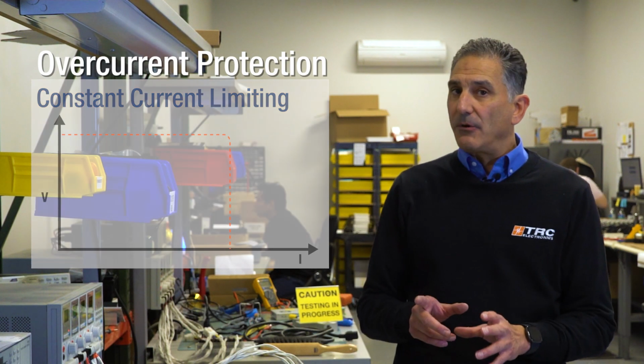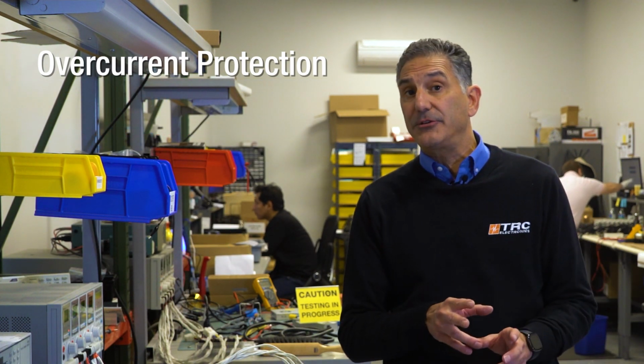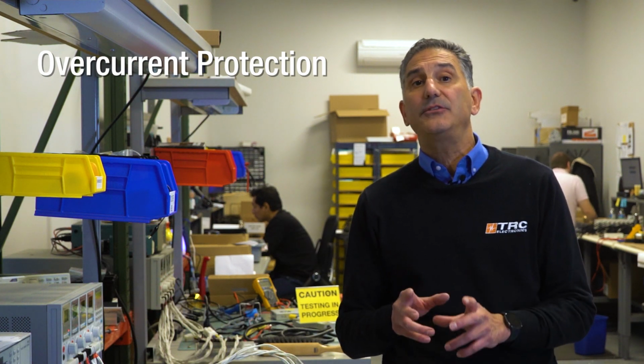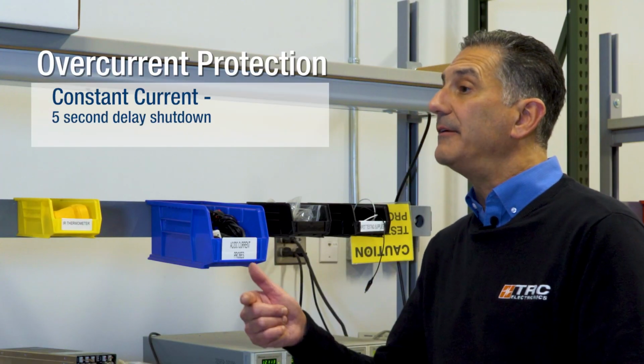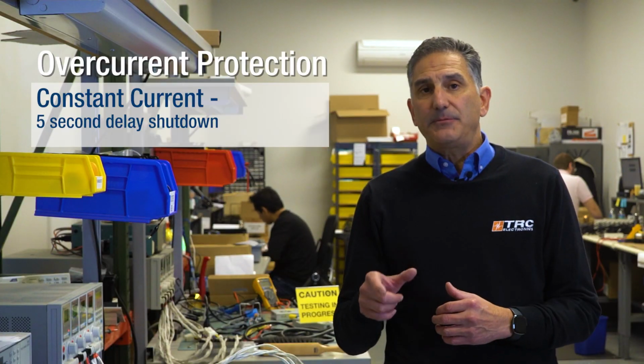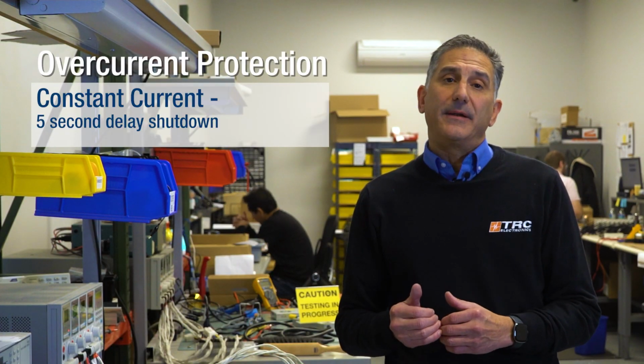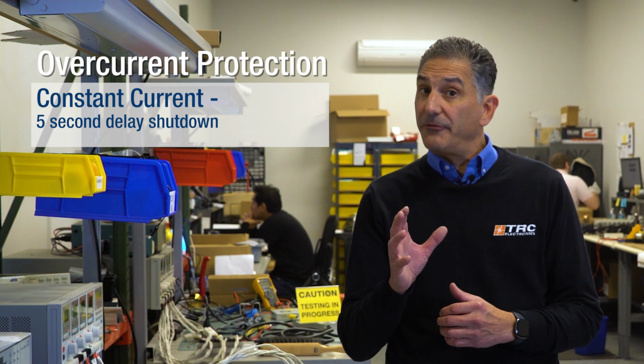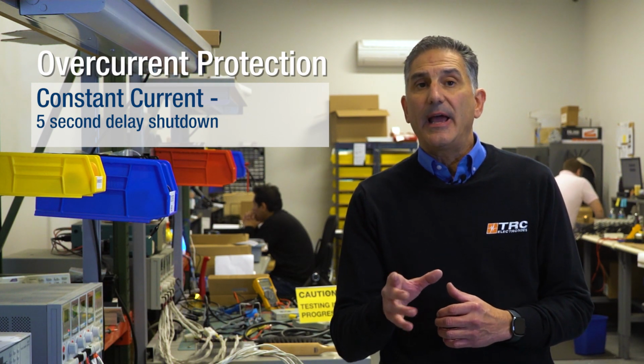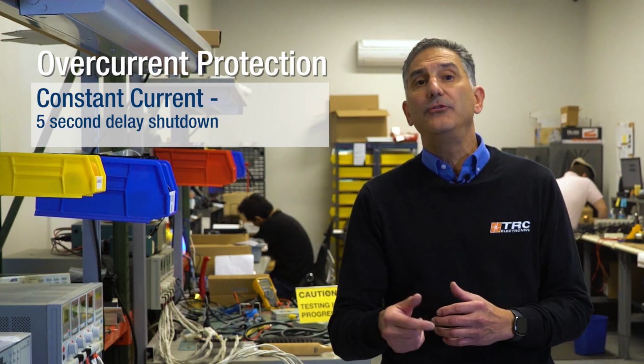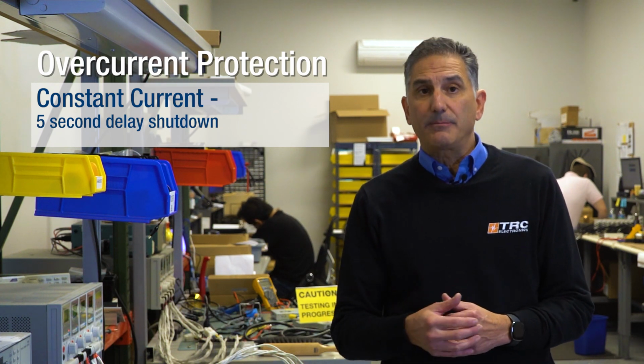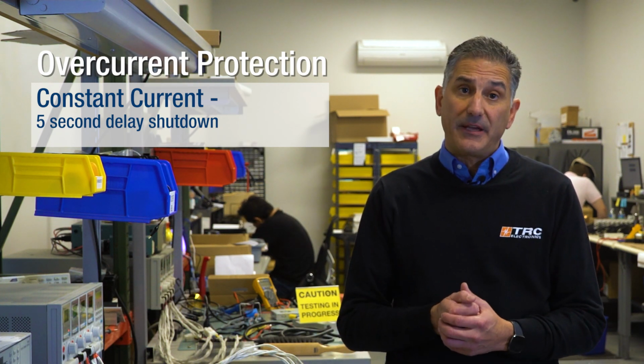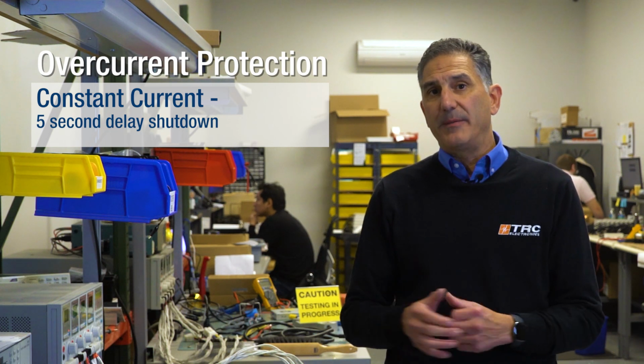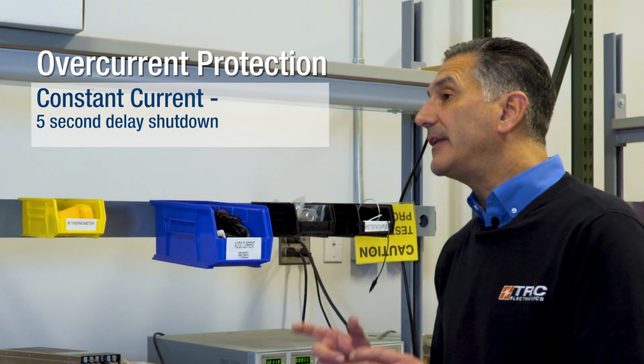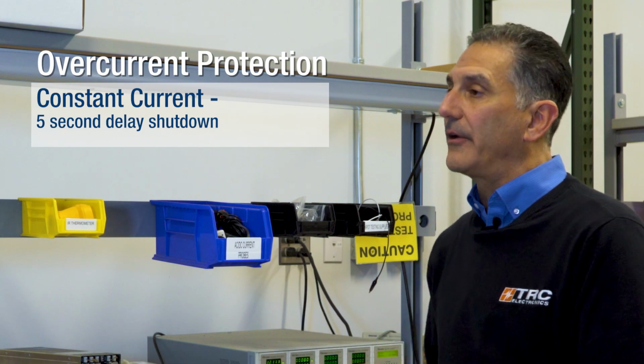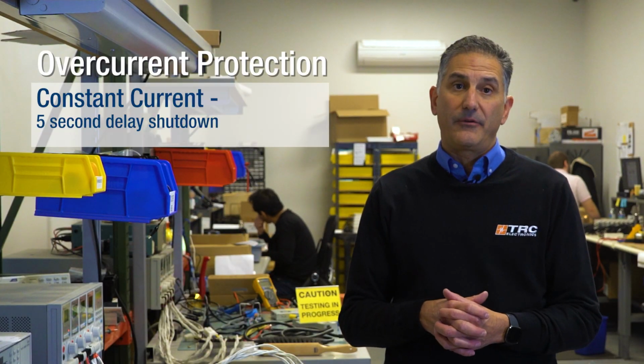Now, some power supplies that have constant current features also have a constant current feature with a 5-second delay shutdown. In this specific feature, what will happen is the power supply will shut down after 5 seconds of constant current, and in some cases, in order to restart the power supply, you'll have to disconnect it from the AC source, wait a couple of minutes, and then reconnect it and make sure that that overcurrent condition is no longer there so that the power supply can react normally.